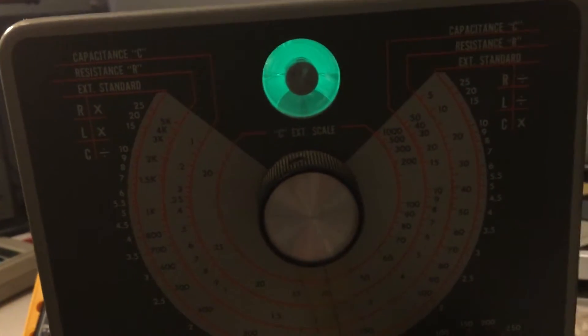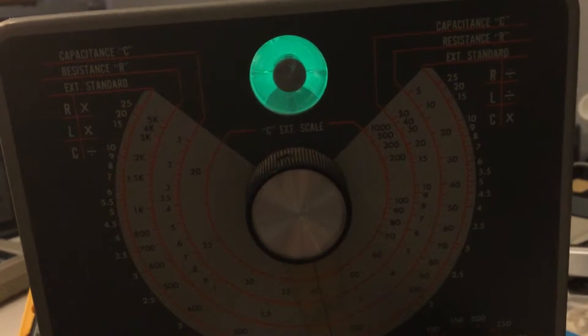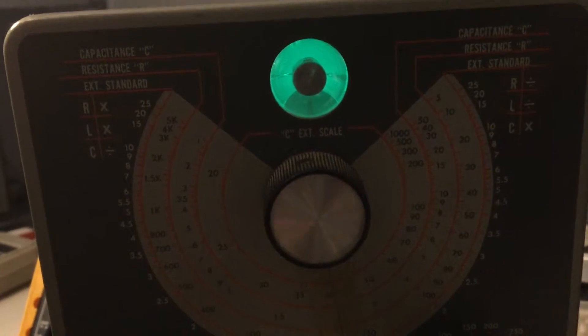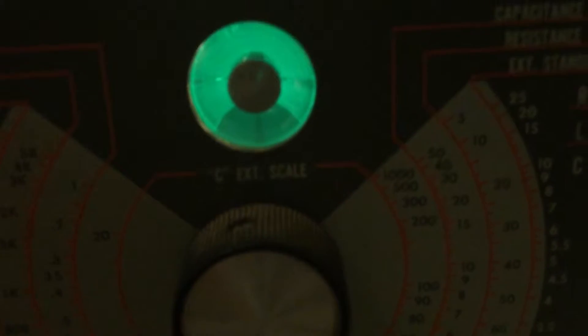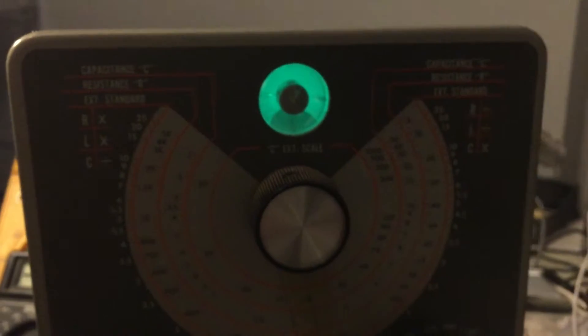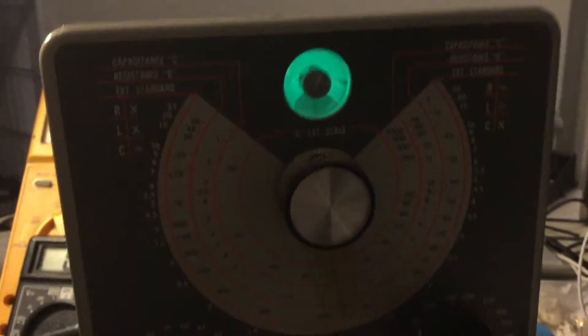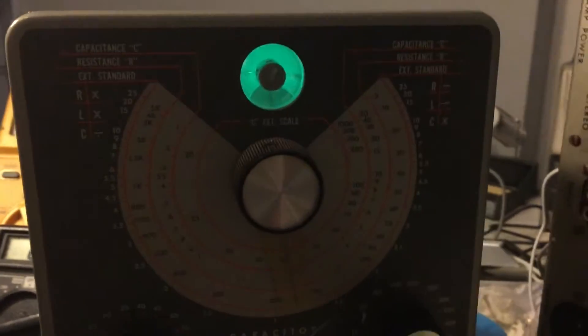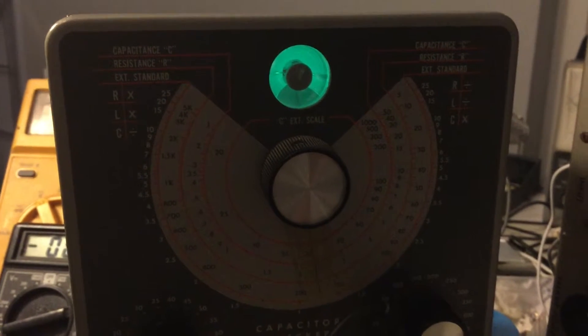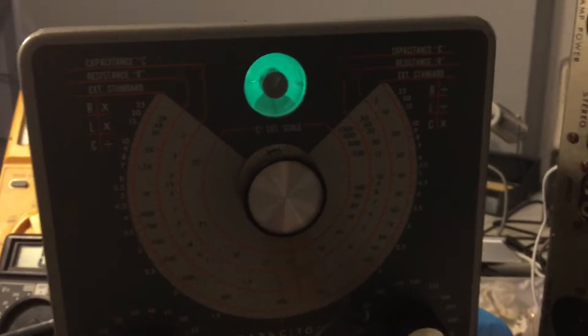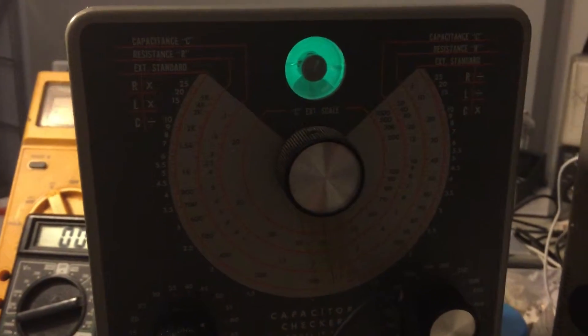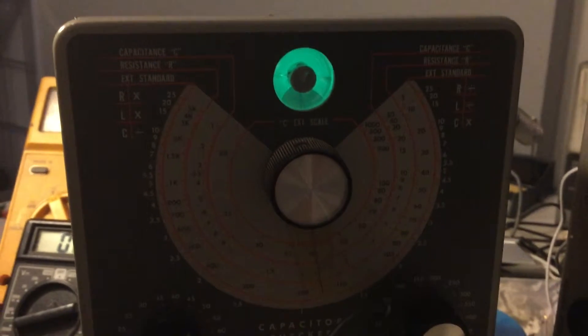It opens all the way at about a thousand microamps and then you'll still see a silhouette on the end and that silhouette disappears at about 800 microamps. So after that after 800 microamps and lower the test set really can't read it and it doesn't really have to because we're talking about an extremely small amount of current.